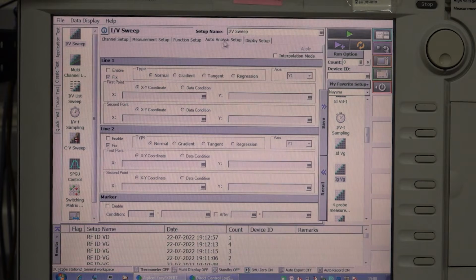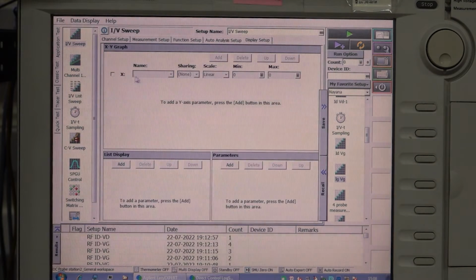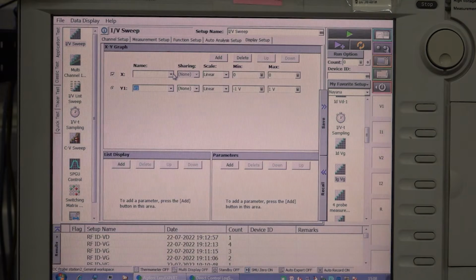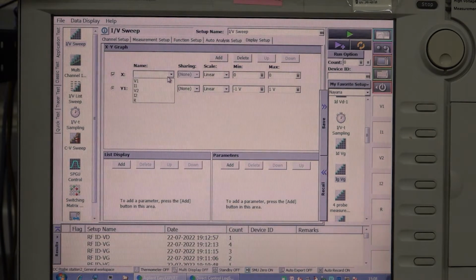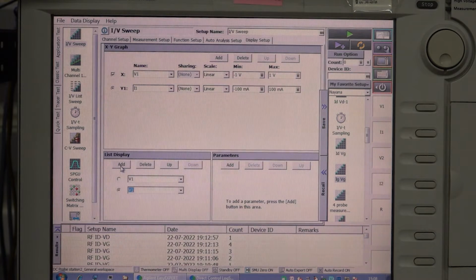So auto analysis setup, basically we have a pre-measured value from the device like a calibration chart. We can compare the calibration chart along with the current measured values. Here we don't have any pre-measured data, so we can go directly to display setup. In the display setup we can basically see the graph plot. So V1 by I1 is my graph plot. List display is nothing but when you export the data, you can see the data in terms of values in CSV format or a text format. So we will get these three columns in the data export.